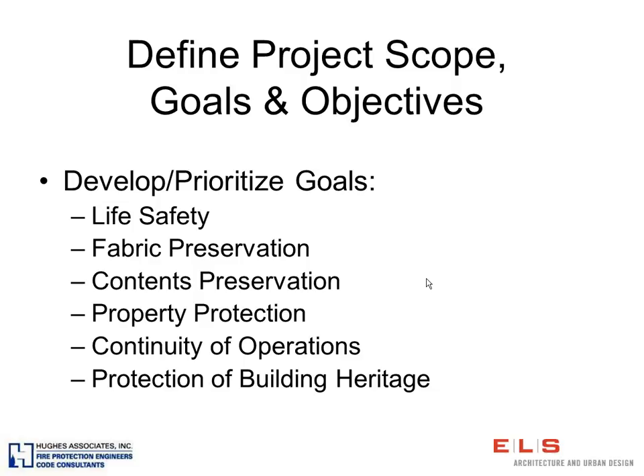For an historic building, or when you are protecting cultural resources, if you are about to embark on a renovation project for them, it's oftentimes impractical or infeasible to comply with the prevailing California building code. In doing so, you may end up disturbing the character-defining features of the building, and that would be an unacceptable approach to take. So when we look at protecting the building, the first step that we need to take is to sit back and take a look at the goals and objectives that we're trying to accomplish and determine how we can provide a reasonable level of life safety while at the same time maintaining the character-defining features within the building. The California Historical Building Code gives us tools to do that, and we also use our, as fire protection engineers, knowledge and experience working with the design team to come up with an approach that's acceptable.